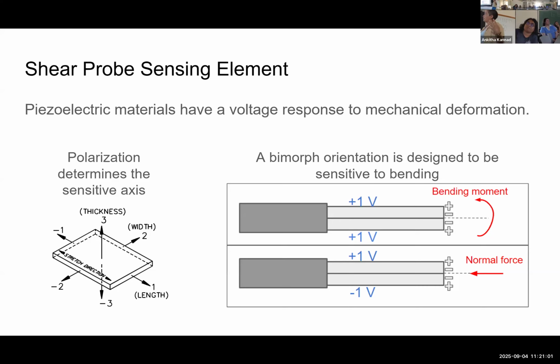Stepping backwards a little bit to why an ADCP and a shear probe work, they're actually made of the same type of material. It's called a piezoelectric material. When a piezoelectric material experiences any kind of mechanical deformation, you get a voltage response out of it. And it also goes the other way. The way that an ADCP works is that you have this little circular disc, which is made of a crystalline material that has this piezoelectric property. When you send a voltage to that piezoelectric material, it vibrates. That vibration pushes on the water and creates a sound wave. So that's what makes the ADCP produce sound.